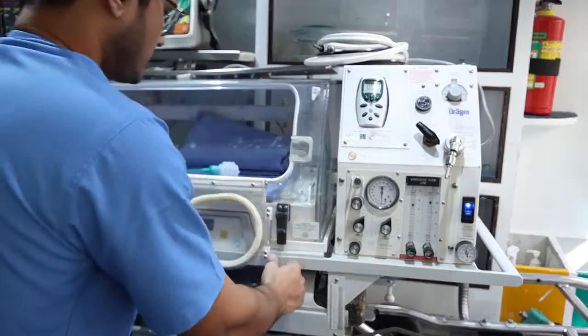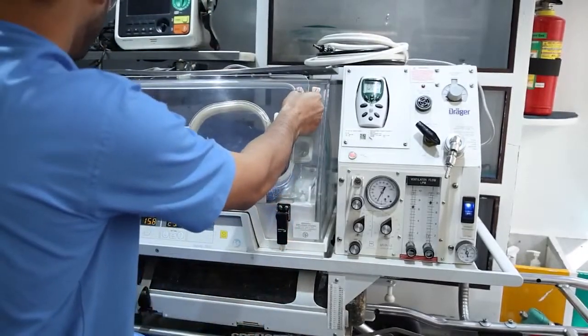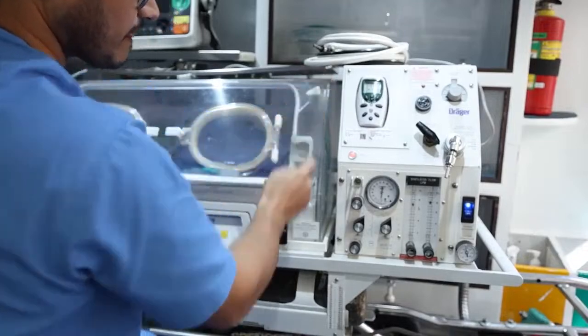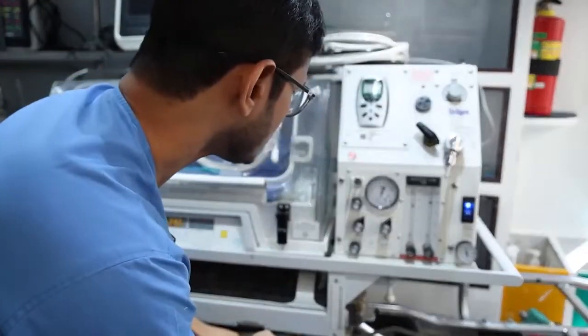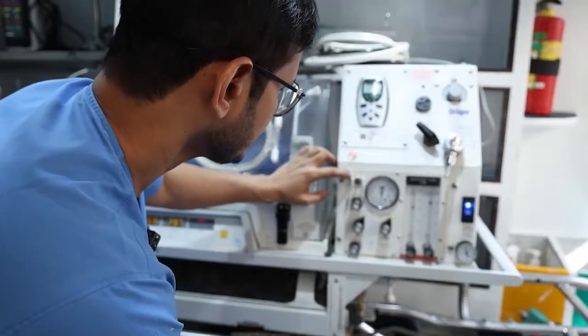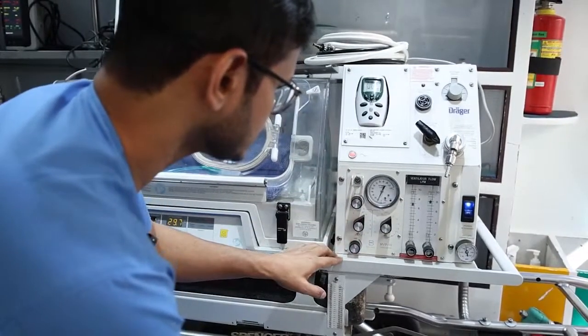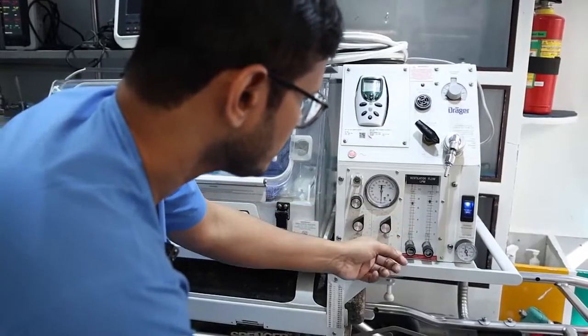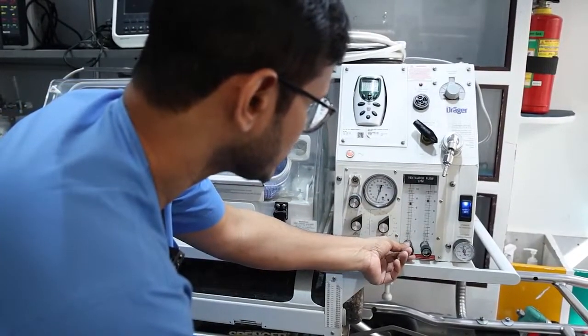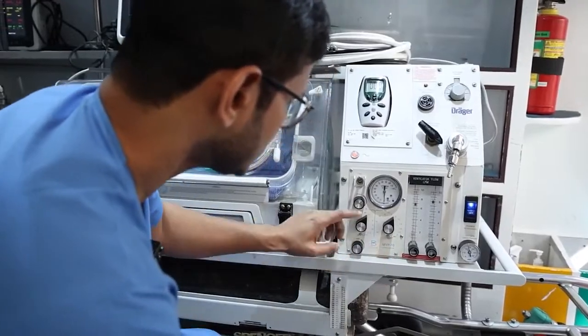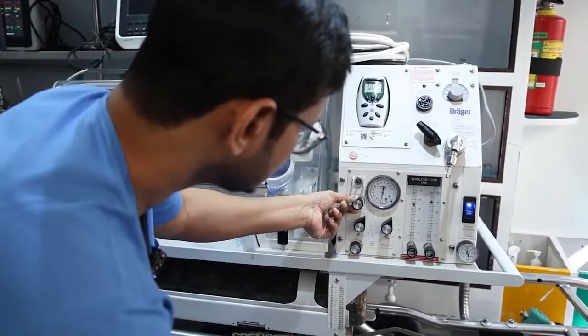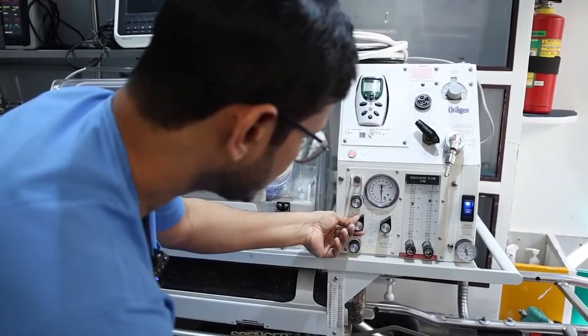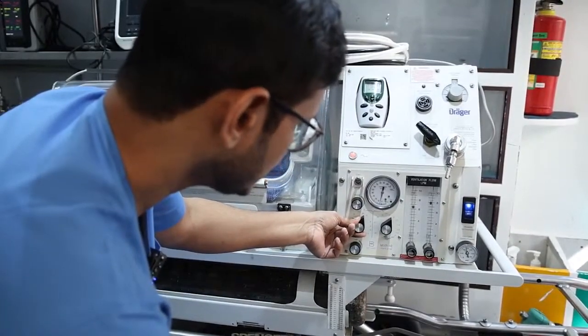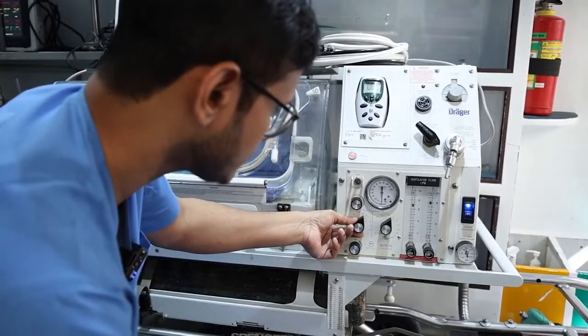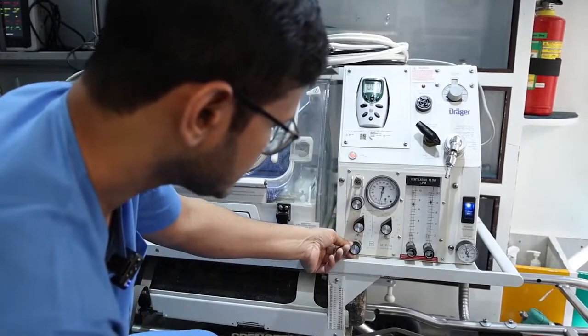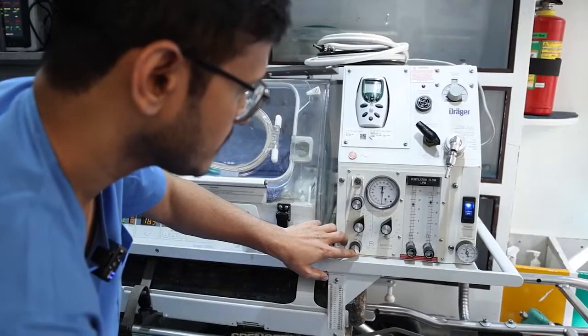Now coming to the ventilator, this Globetrotter has an integrated ventilator system where you see continuous mandatory ventilation, and then there are a few knobs to adjust the settings. Here you can see the ventilator flow where you can adjust the flow to a maximum of 10, and these are the knobs. Here, adjustment of PEEP can be done. Inspiratory time can be adjusted based on the neonatal disease-specific condition. Then the peak inspiratory pressure can be set here.